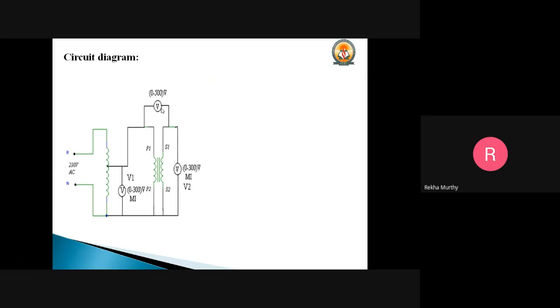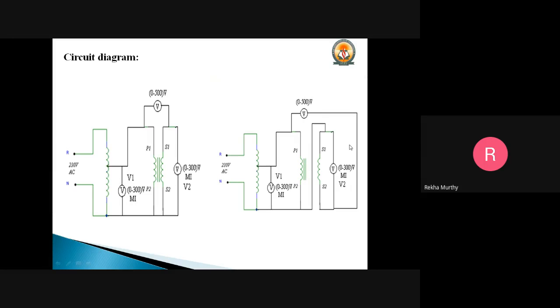If it is reading additive polarity, we don't want it to read double the voltage, so we need to interchange the secondaries of S1 and S2. When you interchange, the circuit connection changes into this fashion. Again you observe the voltmeter, and it will read subtractive polarity, that is a 0 value.